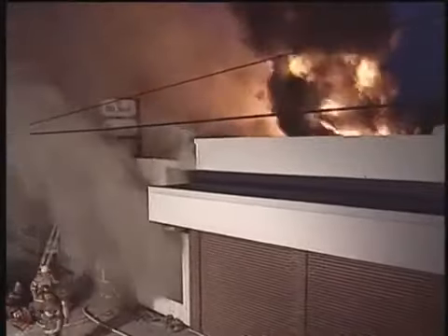Dense smoke often has carbon particles and moisture in it, which can become energized and produce a potentially lethal arc. If overhead wires are present and the volume of fire is great enough, the wire's coating can burn and the wire may fall, leaving you with two extremely dangerous hazards.